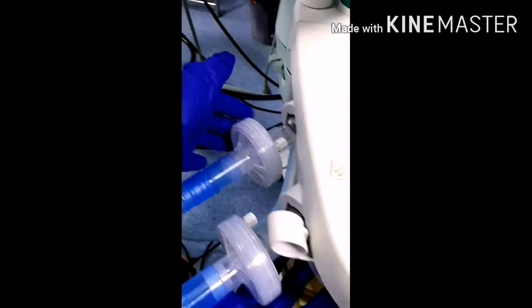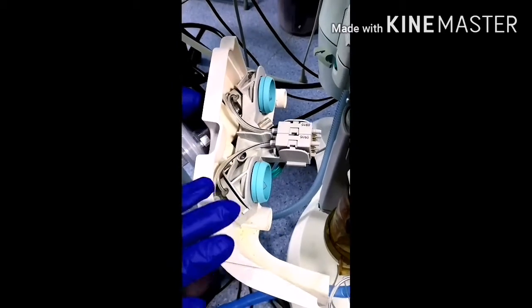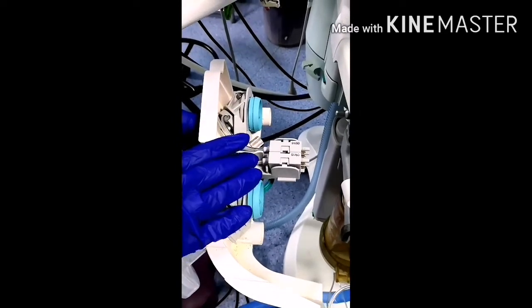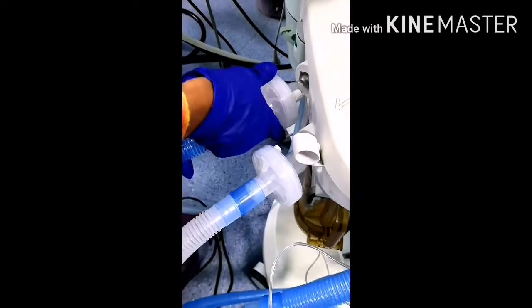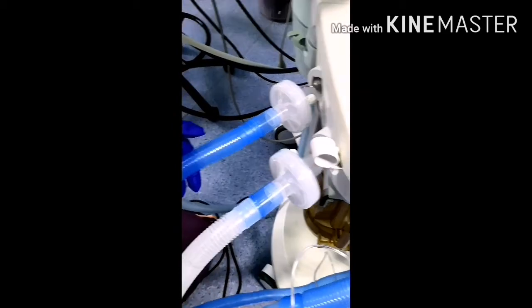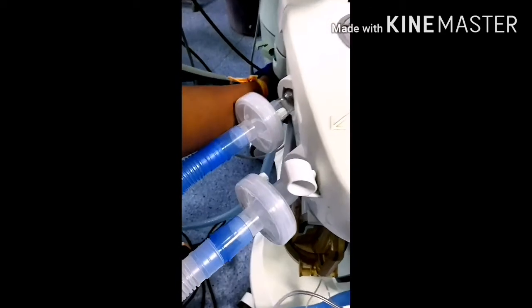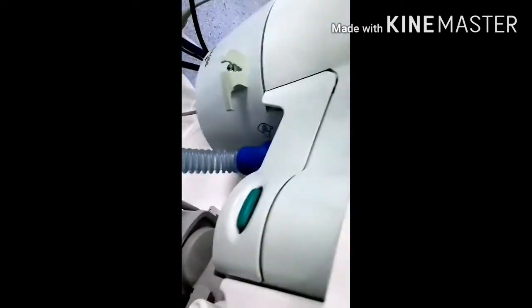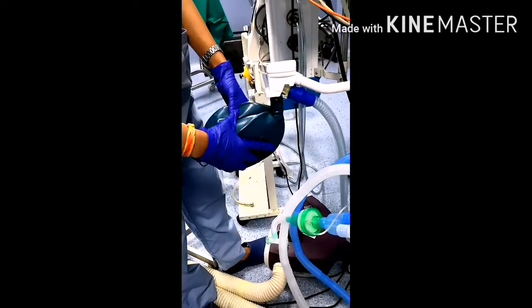Over here, you can see this is the flow sensor. This is the flow sensor of the machine, which detects and senses the tidal volume that has been achieved. It gives us a digital value on the screen about how much the tidal volume has been set and achieved. Okay, this is the inspiratory supply and this is the expiratory, like the gases flow to the patient and from the patient it comes back to the machine. Okay, and here this is for the bag supply. You connect your tubing just below the breathing circuit and you attach your bag. This is an AMBU bag for manual respiration which has been used.